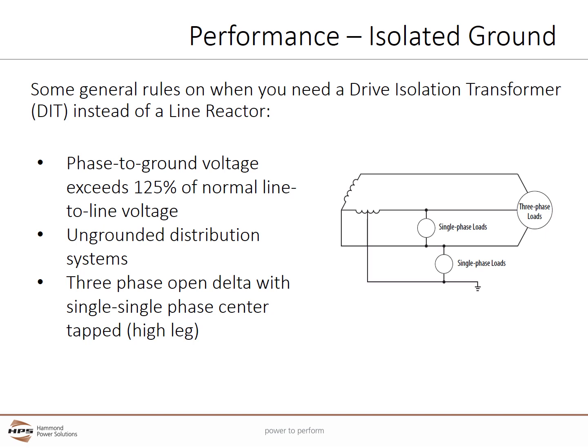Let's talk about isolated grounds further. Here are some general rules on when you need a DIT instead of a line reactor. If the phase to ground voltage exceeds 125% of normal line to line voltage, or if you are using an ungrounded distribution system, or if you are using a 3-phase open delta system, especially with a single phase center tap high leg. An open delta system is pictured on the right.